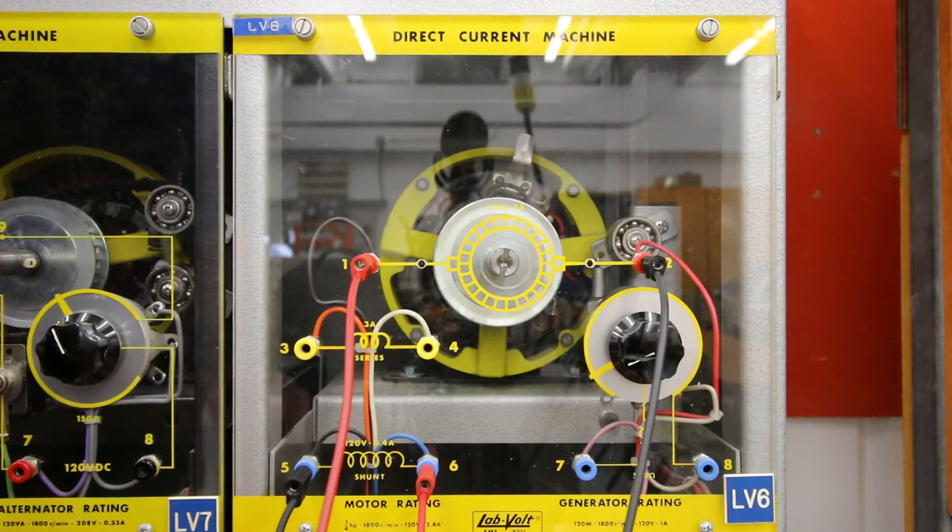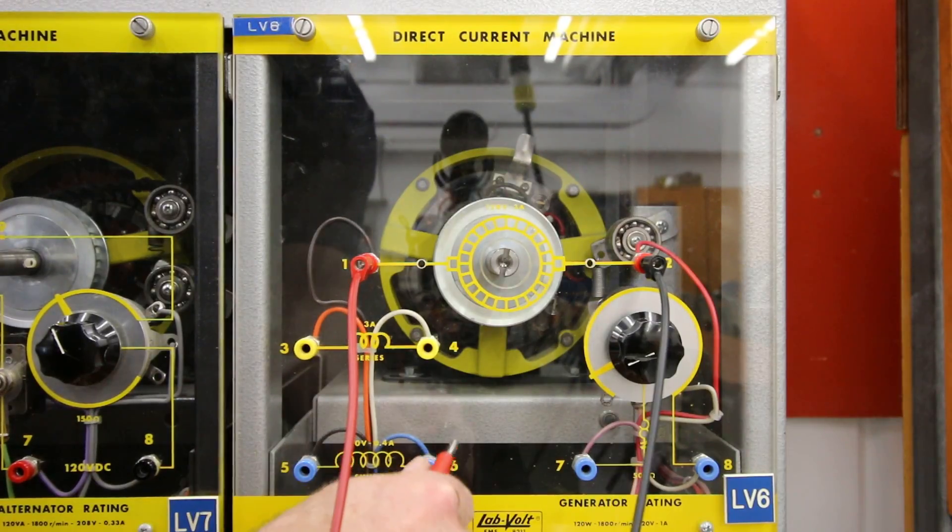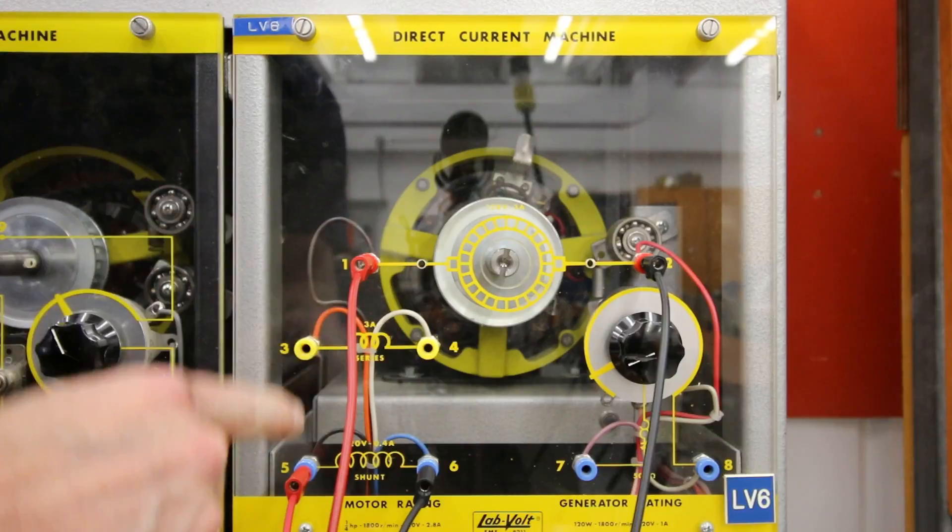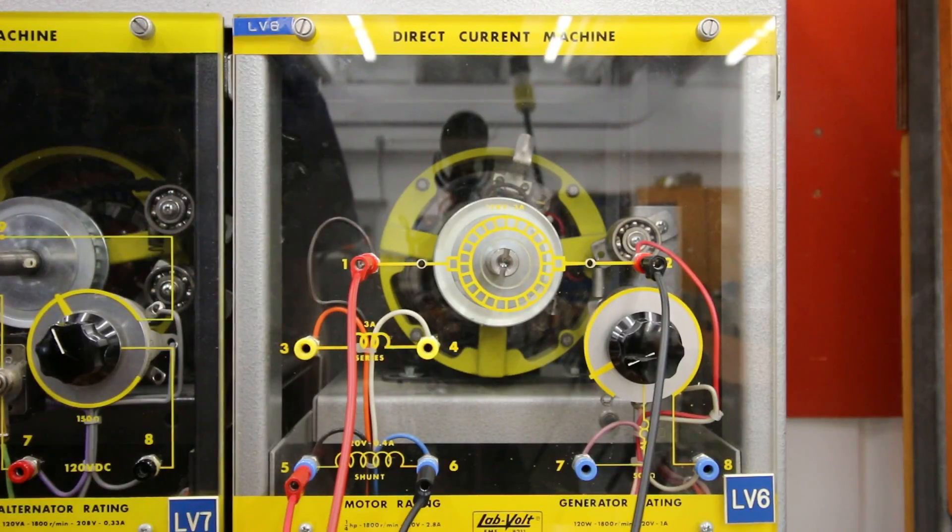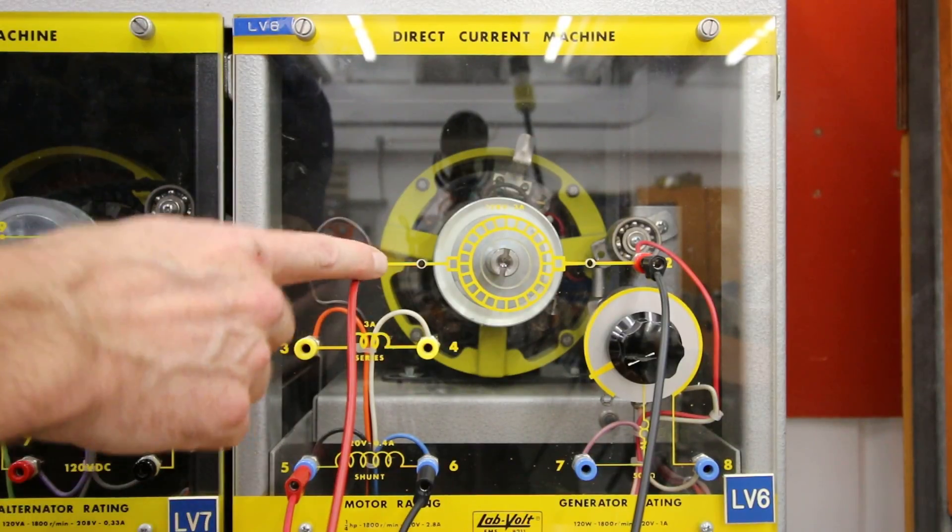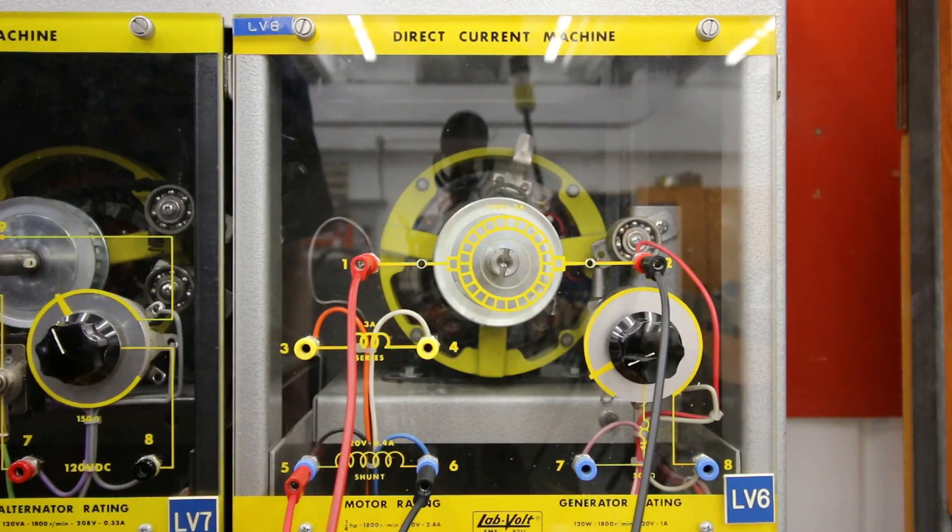So, in order to change the direction rotation of a shunt motor, I can change either the armature or the shunt field polarity. Convention is to change the armature, though.